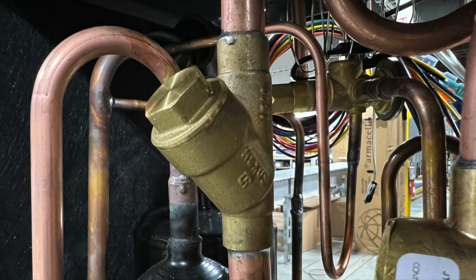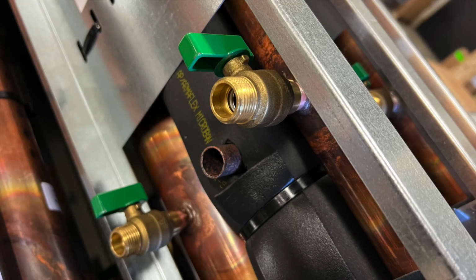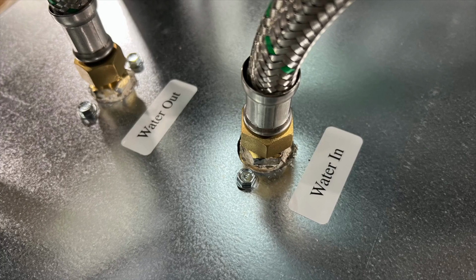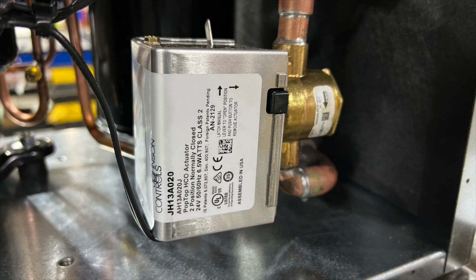If the unit that you're working on has a flow control valve, make sure the inner components are installed properly and there is no debris blocking flow. Make sure both riser ball valves are on and the flow is not reversed. The cooling actuator should be energized and passing full flow. The heat actuator should not be energized and should have no flow through it.